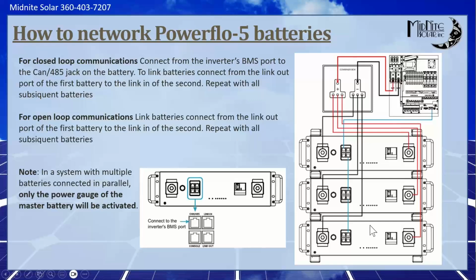There are no dip switches, no programming - it's all automatic. That one battery, that's how it determines who is master. So when in doubt, look for which battery has the empty link in port on the upper corner - that's your master, the one you push the power button on, only that battery. If you're running open loop, you still connect the link in and link out together like this, and you still press the one button - you just don't have the closed loop.